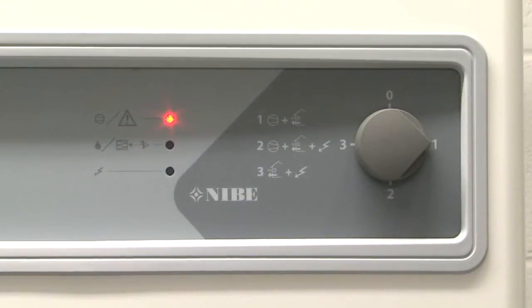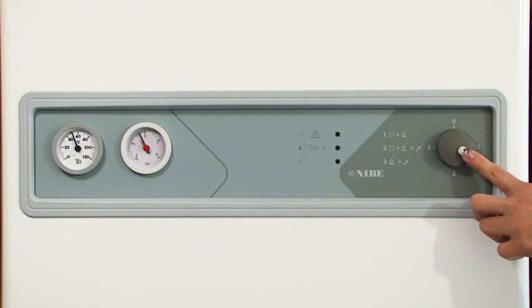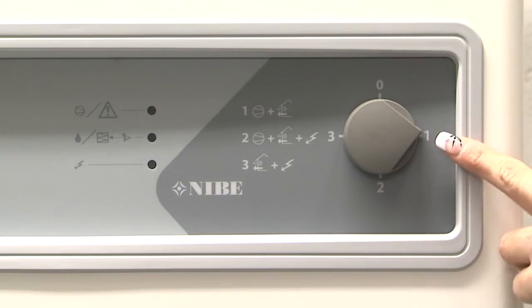If there are lights that are flashing, this can be a notification that there is a filter to check or that there could be a problem with the system, in which case consult your installer or housing association. To the right of the lights is the main control knob. Number one on the control knob is referred to as the spring/autumn setting and is to be used through the warmer months of the year. Setting one relies on the heat pump only to provide heating and hot water.